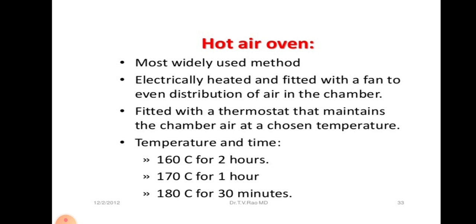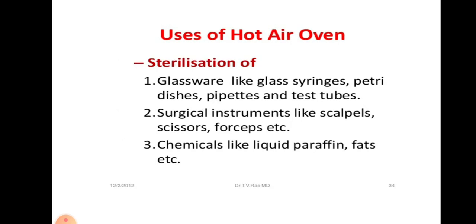The hot air oven is fitted with a thermostat that maintains the chamber's air at a chosen temperature. It can be used with three different temperatures: 160 degrees centigrade maintained for two hours, 170 degrees centigrade maintained for one hour, and 180 degrees centigrade for 30 minutes to achieve sterilization of inserted glassware. Uses of hot air oven include sterilization of glassware like glass syringes, petri dishes, pipettes and test tubes. Surgical instruments like scalpels, scissors and forceps are also sterilized in the hot air oven. Chemicals like liquid paraffin and fats are also sterilized in this hot air oven.